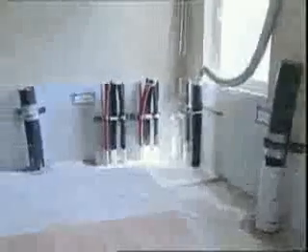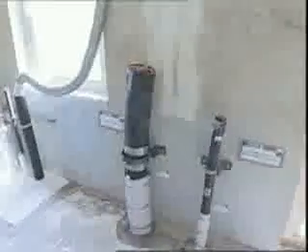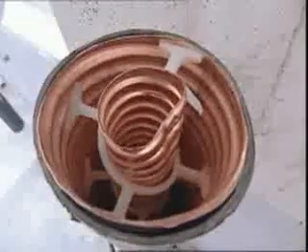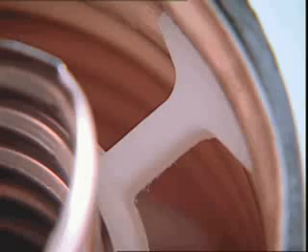The broadcasting cables end here. A good opportunity to have a look at their insides. Highly dangerous in a fire are the plastic distancers made of polyethylene between outer and inner copper pipe. Once they ignite, burning plastic will start dripping without hindrance.